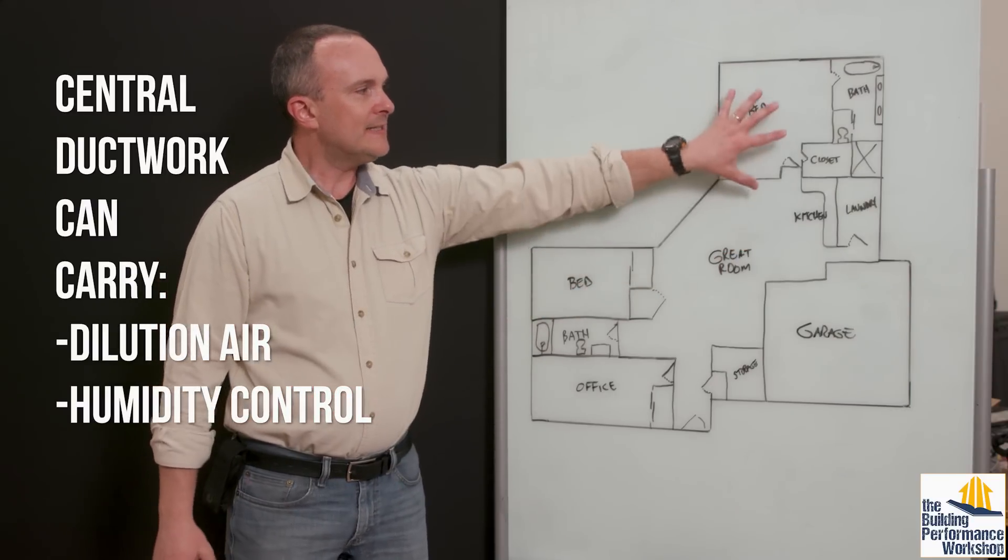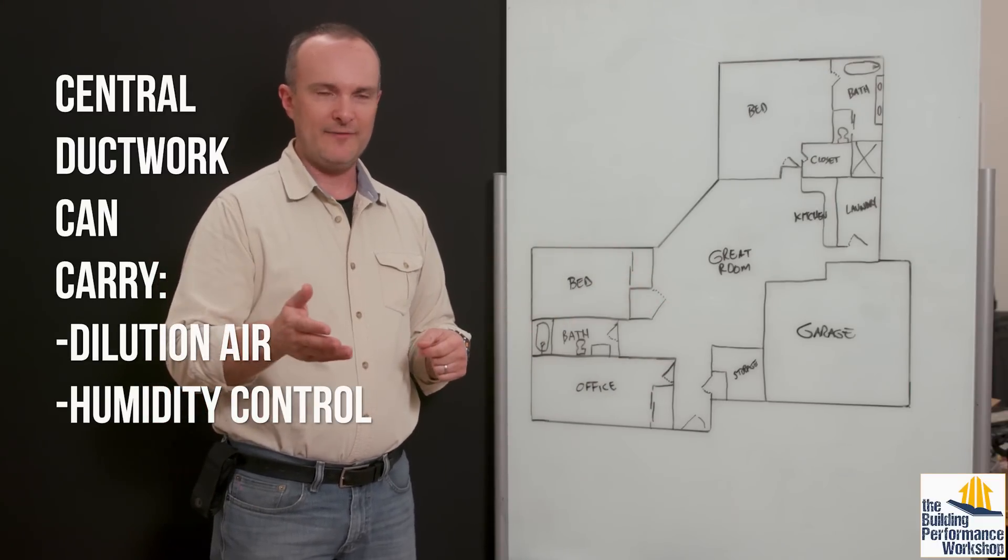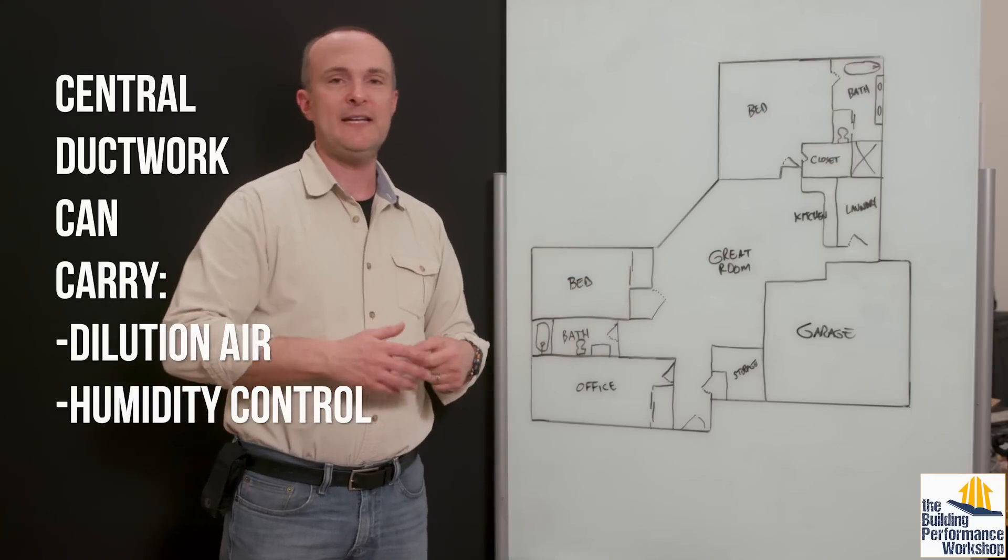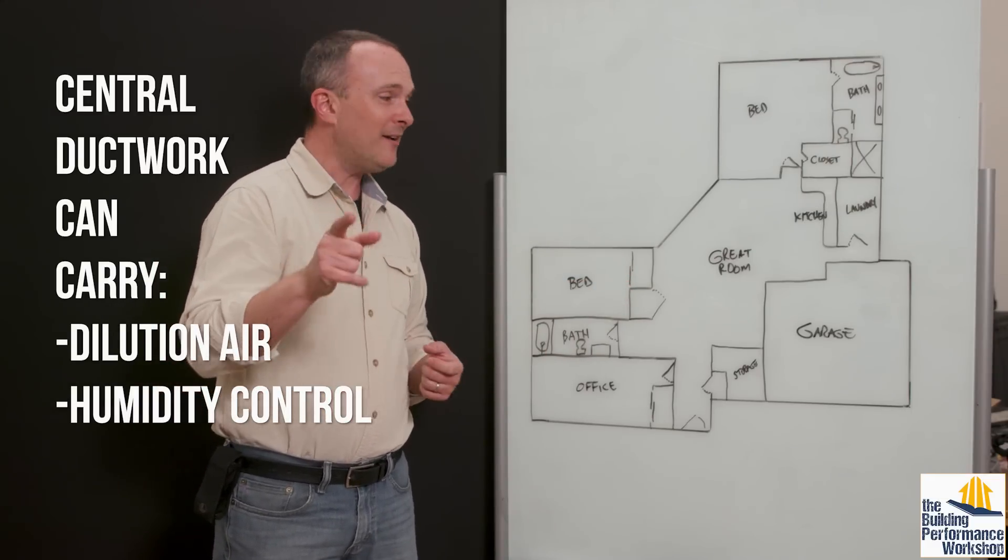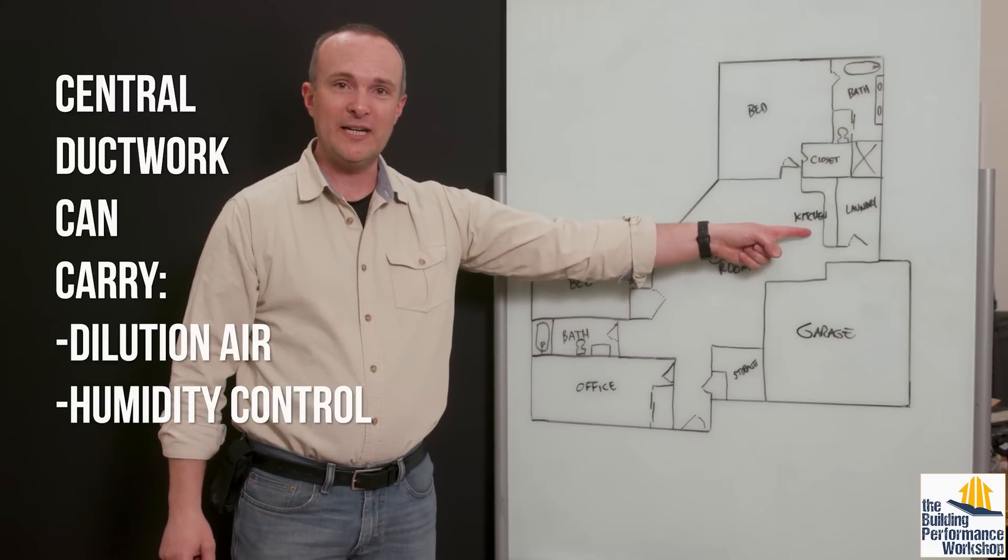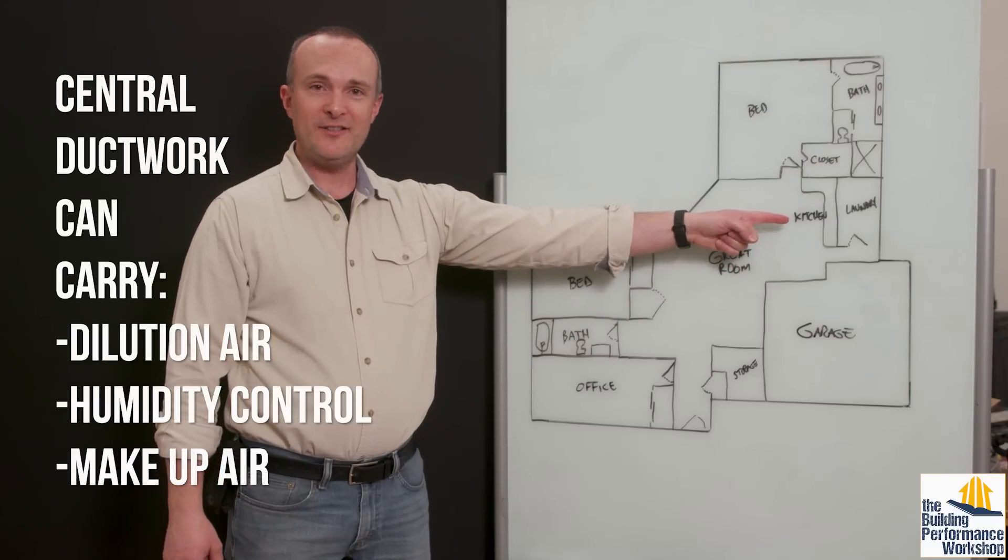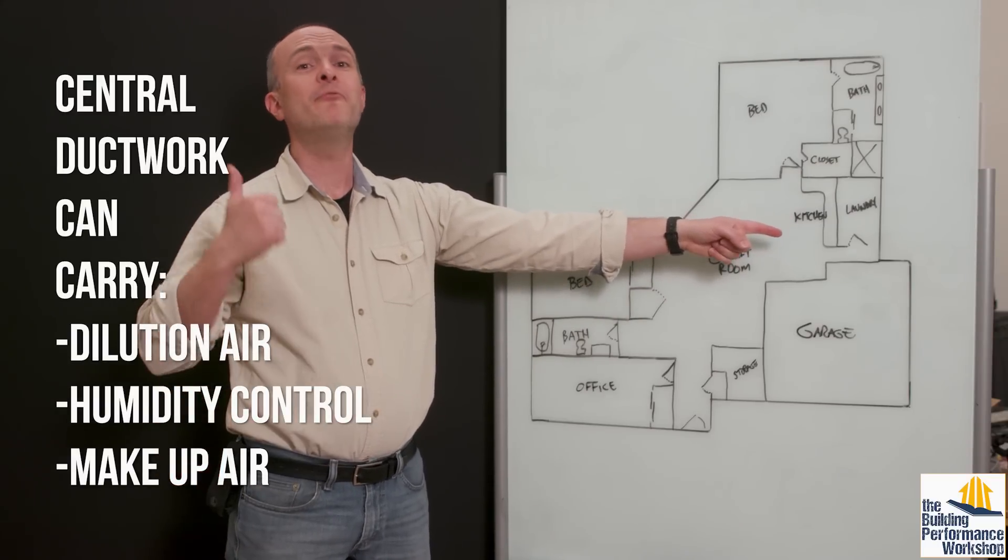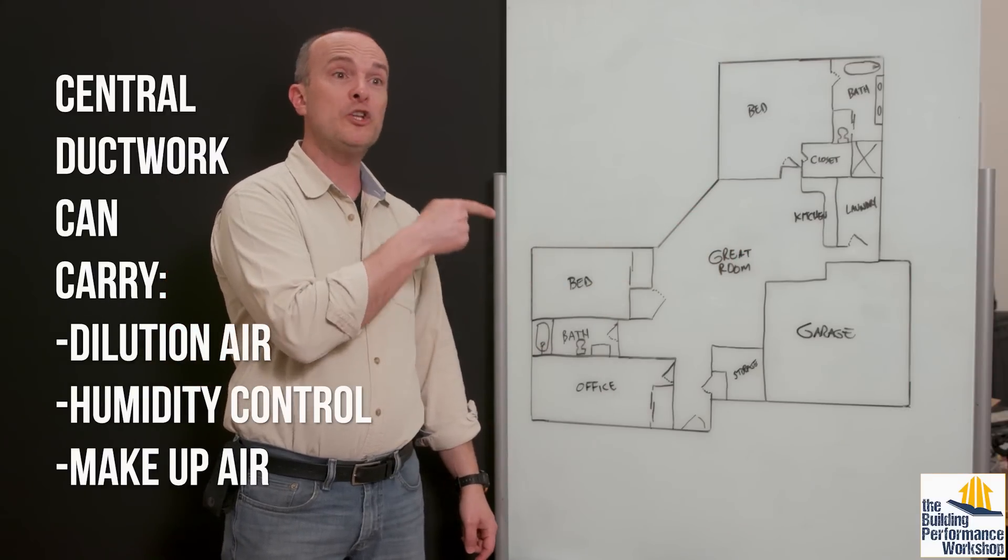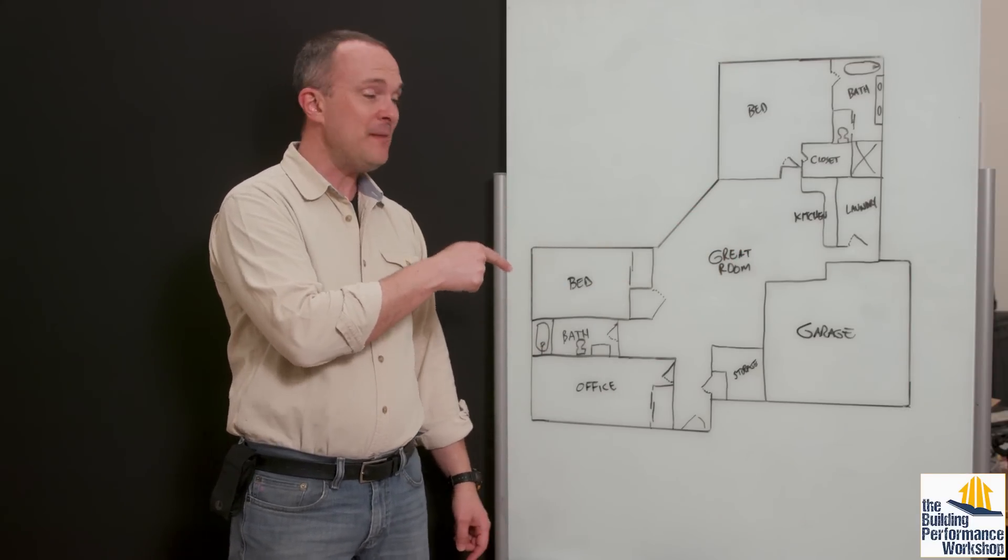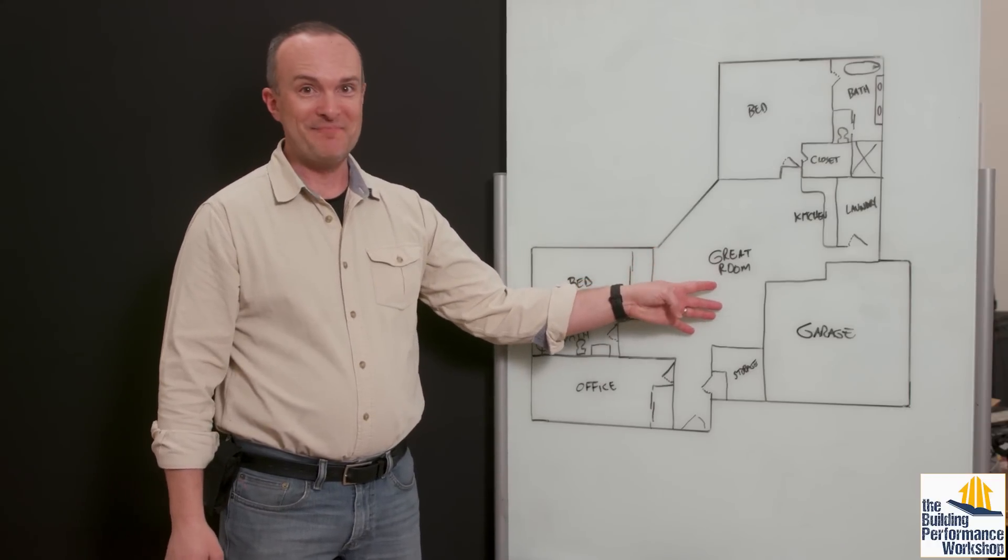So this duct system might not just deliver 600 CFM of heating and cooling, that ton and a half. It might also deliver 350 CFM for the dehumidifier. It might also deliver 150 CFM for your ERV. It might also deliver, in our case of our kitchen over here, makeup air because our kitchen is going to have an exhaust hood in it that goes outside and it's going to dump 400 CFM outside. That 400 CFM in a house like this, which the blower door test on this house might be 400 CFM 50.